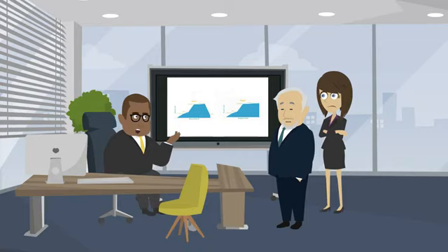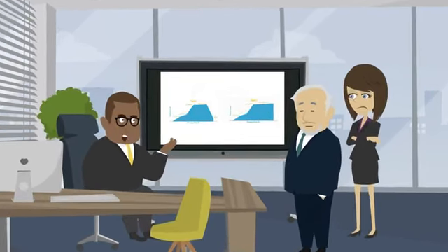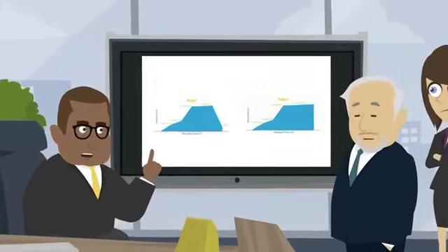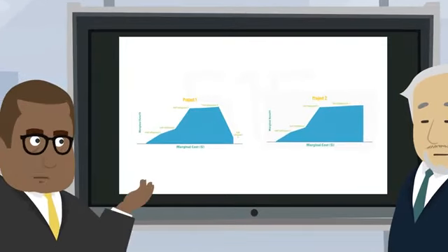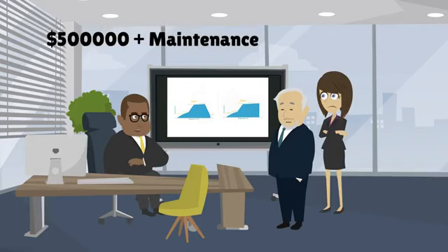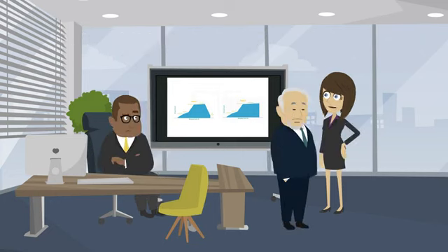I was reviewing your project budgets last week, and I noticed that one well site had to implement a very expensive automatic high-integrity pressure protection system, but the other well site completed last year didn't have this protection system. The additional safety function will add $500,000 to the project, plus additional ongoing maintenance costs. I thought that the design basis for both of your projects was fairly similar, so I was just wondering why there is this significant difference. Your project doesn't need the additional safety function for overpressure protection? What is the risk without it?